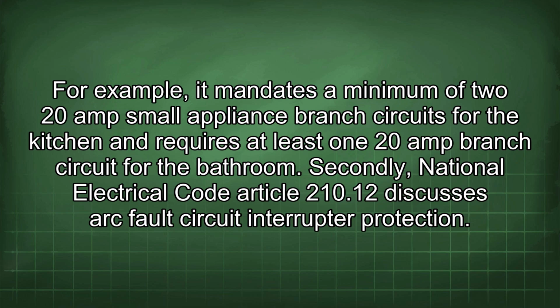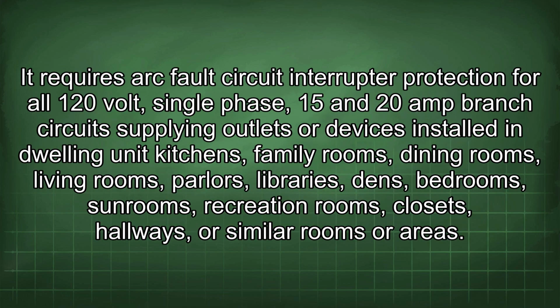Secondly, National Electrical Code Article 210.12 discusses arc fault circuit interrupter protection. It requires arc fault circuit interrupter protection for all 120-volt single-phase, 15 and 20 amp branch circuits supplying outlets or devices installed in dwelling unit kitchens, family rooms, dining rooms, living rooms, parlors, libraries, dens, bedrooms, sunrooms, recreation rooms, closets, hallways, or similar rooms or areas.